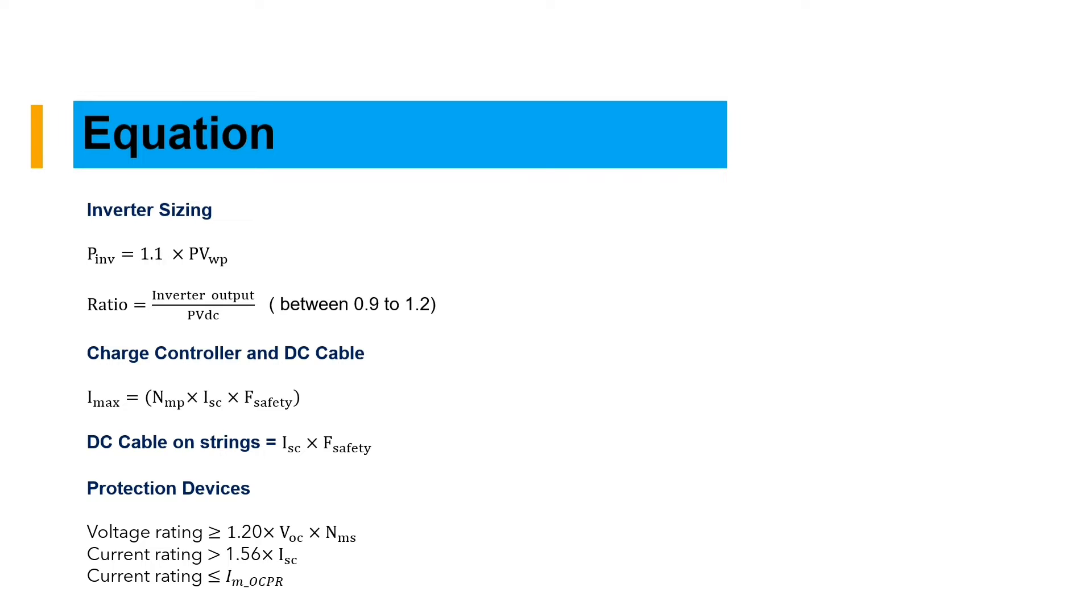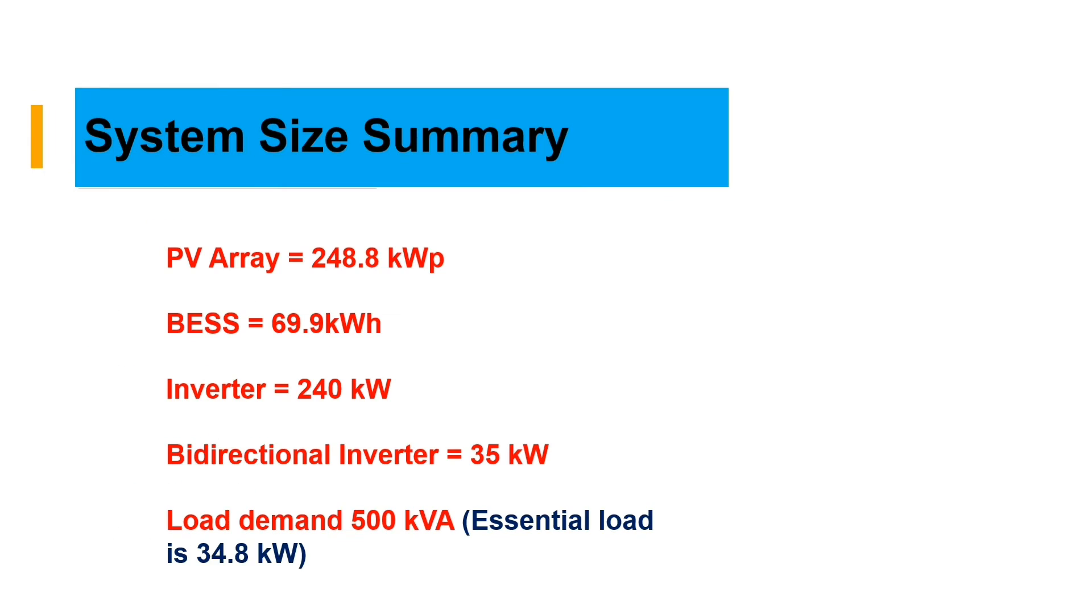Protection device voltage rating should be equal or greater than 1.2 times the open circuit voltage of the module times the number of modules in series. The current rating should be greater than 1.56 times Isc short circuit.